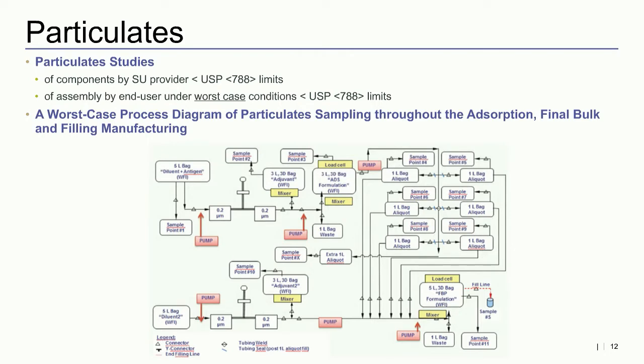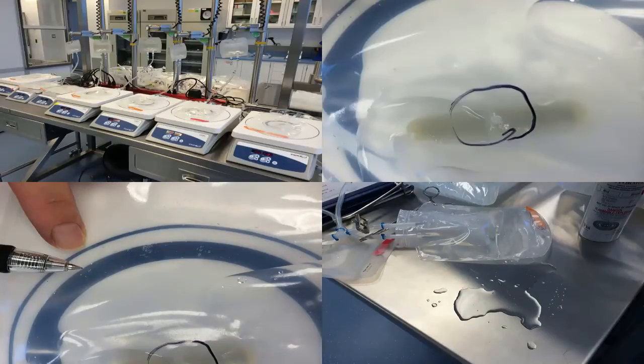I should also add that we also tracked the particle sizes that were smaller than 10 microns and larger than 25 microns as well, just to get an idea on where we were standing with respect to particle counts. You can see here, while we were trying to generate our worst case conditions, there's one case where we had some leaking and some particle accumulations within the bag due to mixing under worst case conditions, and they had to be modified in our process so that we got reduced particle counts.